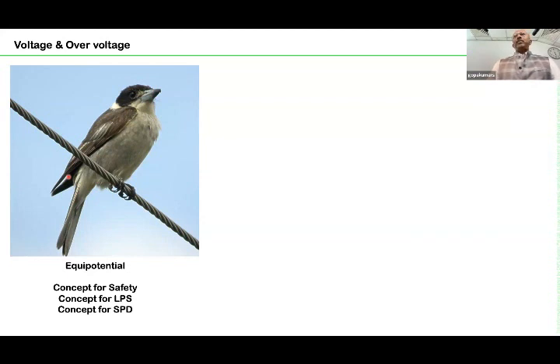for SPDs. Why I am making this statement is, in a lot of places, people buy a good quality SPD, but the earthing wire of the SPD is routed to a separate earth electrode, and they think that lightning current will go through the SPD and go to the earth electrode. It is not like that. You should connect the SPD within the bus bars of the distribution board, for example, and you have to use the shortest wire. So I will explain it later.